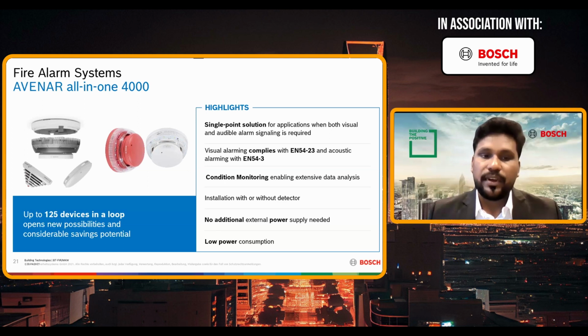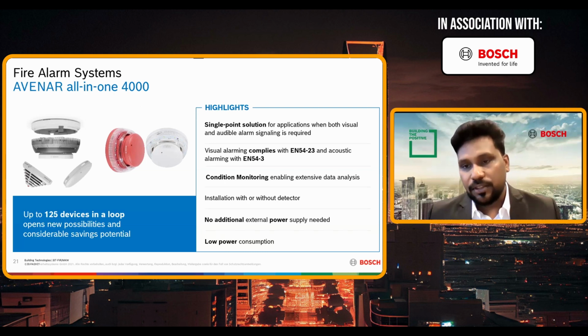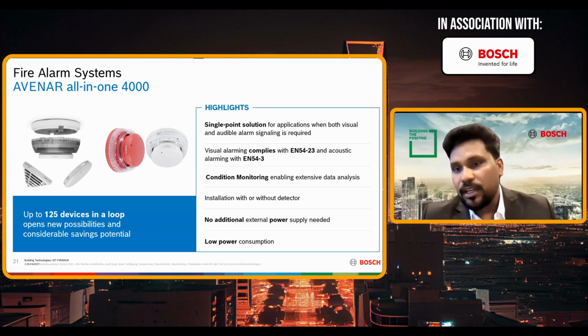You can have 125 sounder strobes with a detector, each carrying different addresses for everything. You can program individually, reduce the number of panels and loops, and the cable requirement will come down so you don't waste the conduit. A lot of benefits come with the Avenar all-in-one series. Also, in case of any cable cut or loss of power, with the battery, the system still keeps working, which plays a very important role in fire alarm systems.